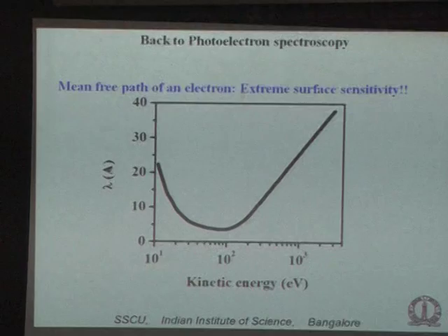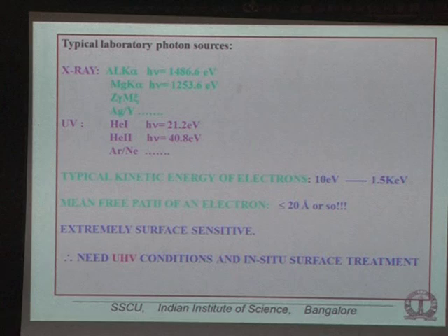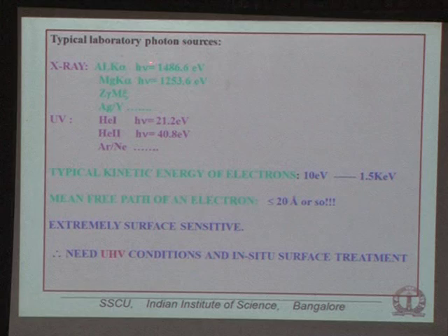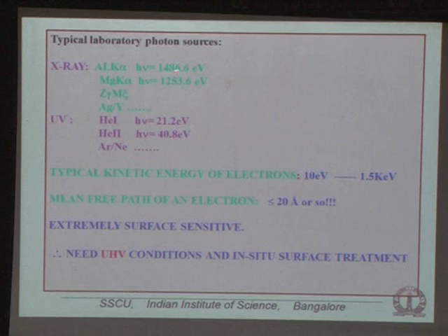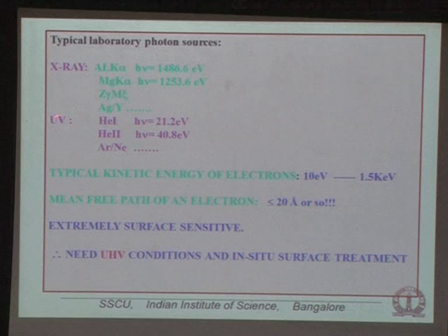It depends on knowing the limitations and how to use the technique properly. Traditionally, the common photon sources were characteristic X-ray emissions — most common was aluminium K-alpha at 1.5 keV energy. Magnesium and calcium K-alpha were also used extensively, as well as zirconium, silver, and yttrium. For low energy work, UV lights — helium-1 and helium-2 resonance lines — are used, and some people also use argon and neon systems, but these two are the most commonly used.